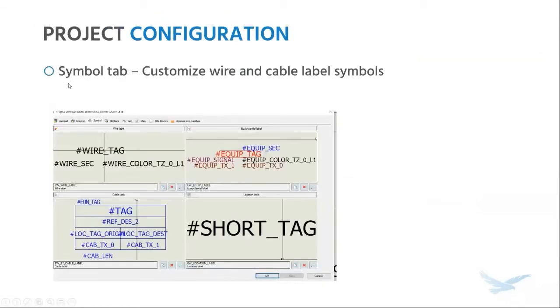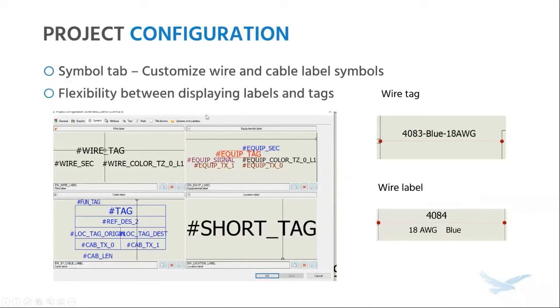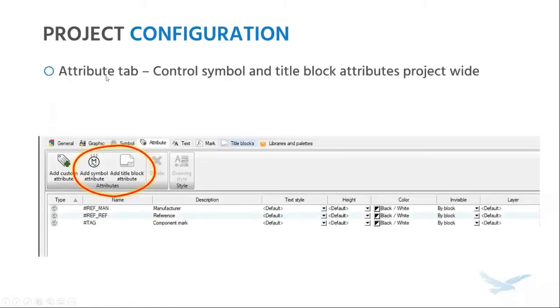Moving to a different tab — the symbol tab — this is a pretty underrated tab, and you can use it to customize wire and cable label symbols. You can either display the wire tag or the wire label. The wire tag is a single entity based off a formula, and that formula could have many variables driving it. If it's a really large formula and you end up with a massive tag on a short piece of wire, that may not look the greatest. So you can opt for a wire label style of display, where all the attributes are laid out around the wire. Depending on the situation, one might give you a cleaner look than the other.